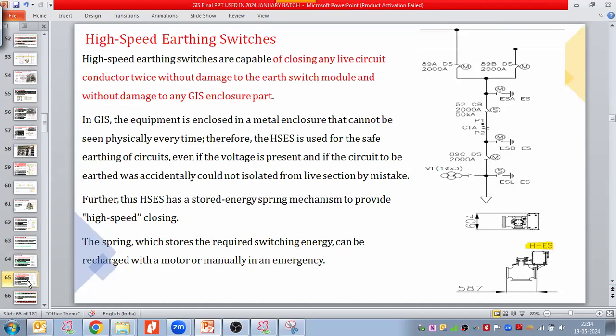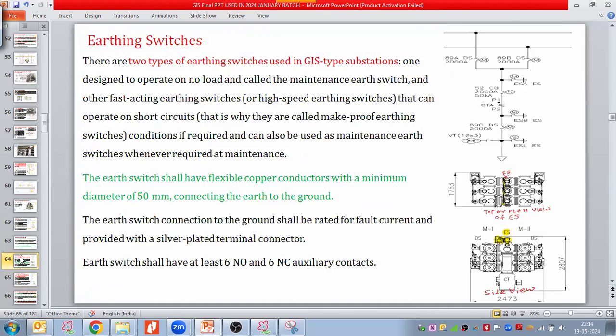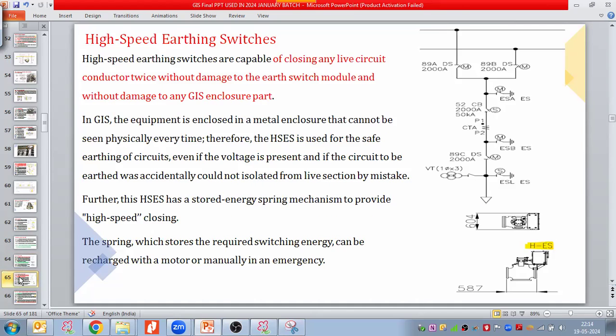So now I hope why we take the maintenance earthing switch is clear to all of you, that we have discussed in AIS module number 4. So now coming to the high speed earthing switch: why we take the high speed earthing switch in GIS and why we do not take high speed earthing switch in the AIS. The high speed earthing switches are capable of closing onto any live circuit conductor twice without damage to the earth switch module and without damage to any GIS enclosure part. This is the feature or facility of the high speed earthing switch.